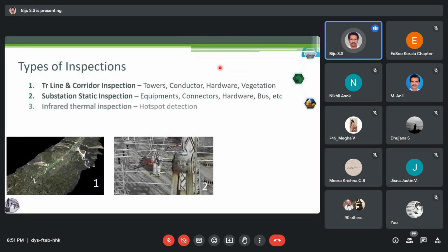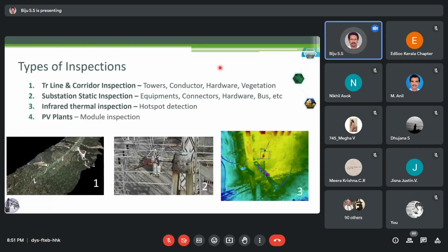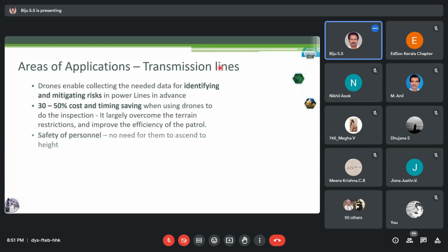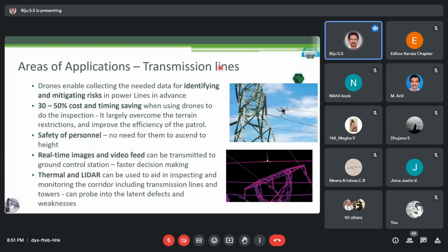Transmission line corridor inspection can be done. Substation static inspections can be done. Infrared thermal inspection of the whole assets can be done. PV plants can also be inspected using drones. And there are 30 to 50% cost and time savings when a drone is used. Safety of personnel is there, and the thermal image camera will detect all the failures also.